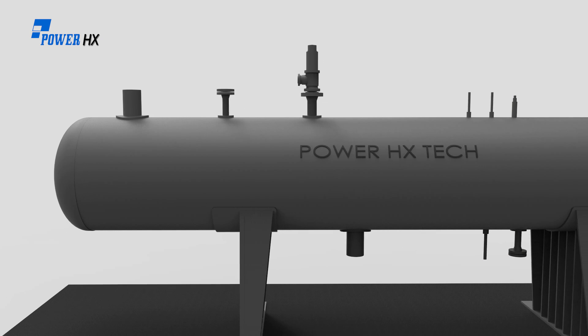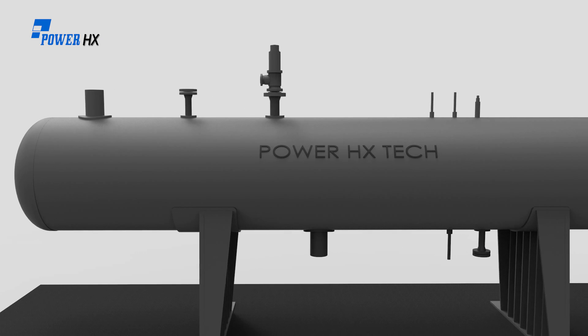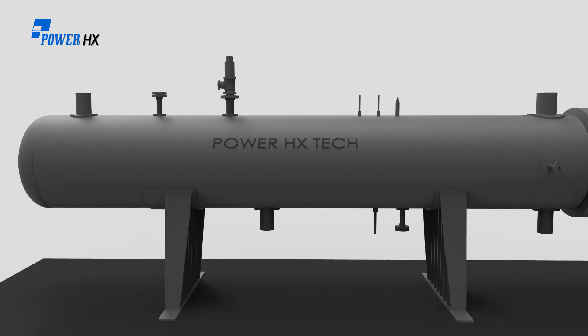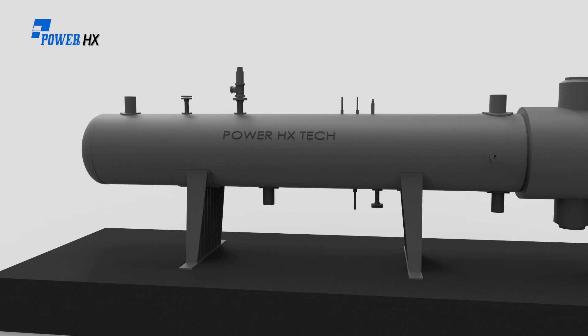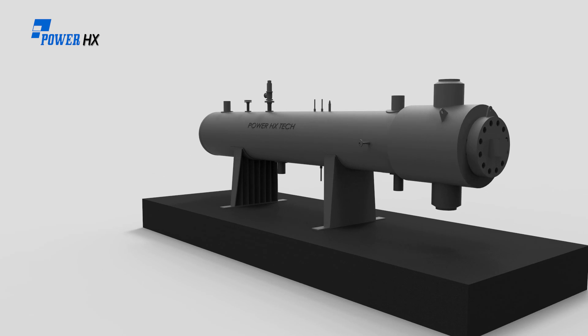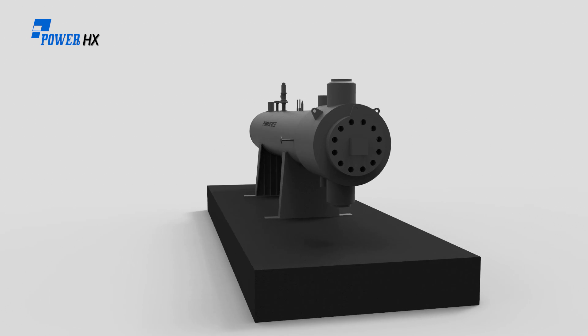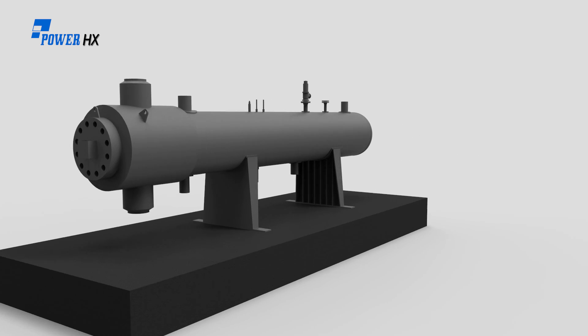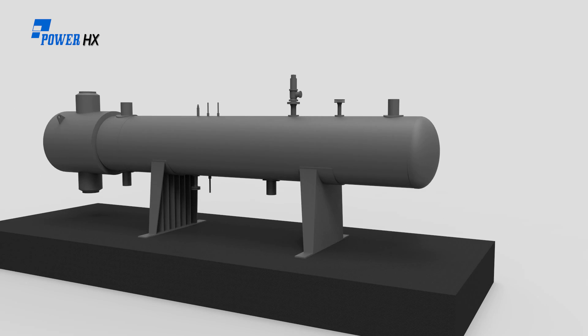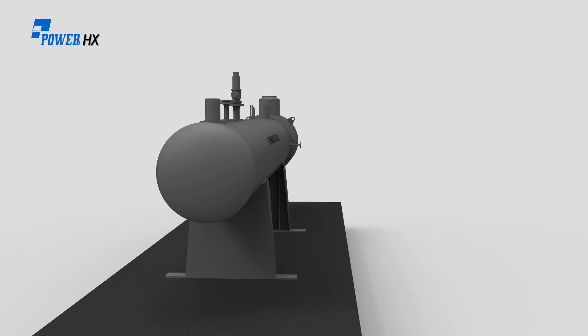A feedwater heater is defined as a shell and tube type unit which heats feedwater or condensate passing through its tubes by means of steam or condensate on the shell side. Feedwater heaters are used in a regenerative steam cycle to improve efficiency. This is accomplished by extracting steam at various points from the turbine and condensing it using boiler feedwater, which reduces fuel consumption.